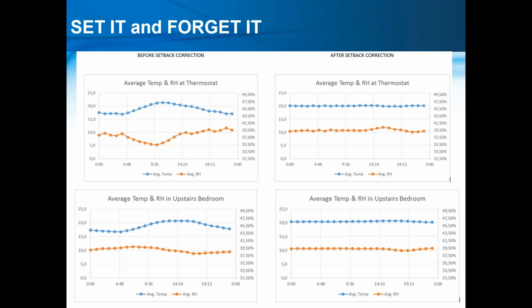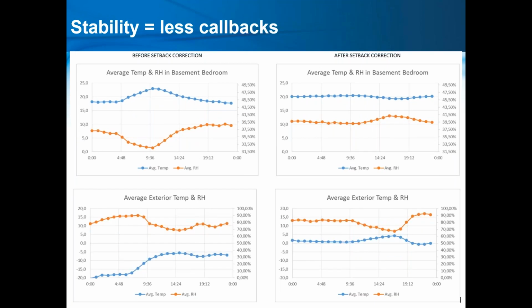So we called Doug and said, hey, turn that setback off on the thermostat. On the right-hand side, you can see now there's a nice balance between the temperature in the house and the relative humidity. Doug brags that he can change the relative humidity in his basement by 8% overnight, so that's it on the top left. After the setback came off, you've got a nice balance there in the house. So yet again, addressing those comfort issues and humidity management. When we can drive humidity management, especially in cooling season, if you're short cycling, the system is turning on and off, and as soon as it turns off, you're uncomfortable again, and when it's on, you're likely freezing. So we want to keep a nice balance by driving that low CFM, longer cycles.